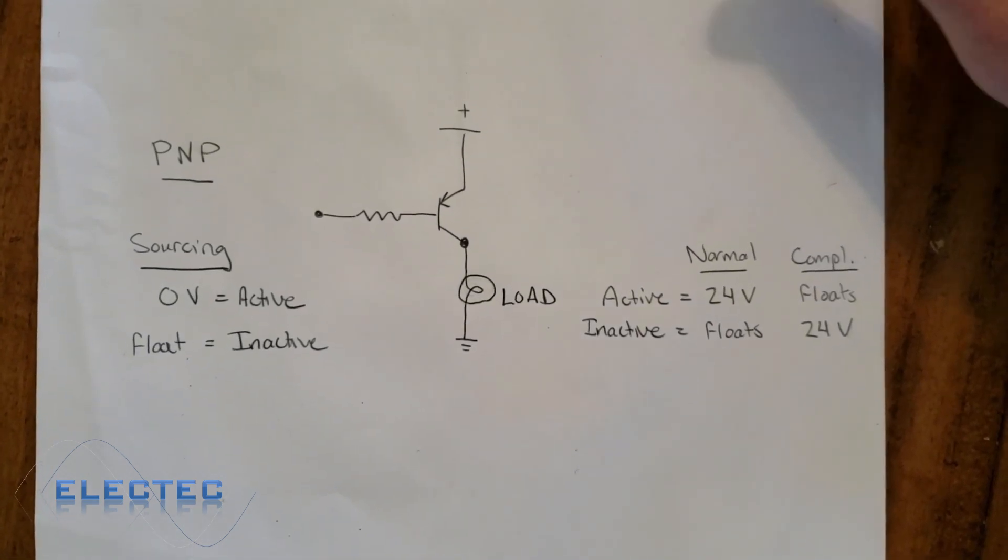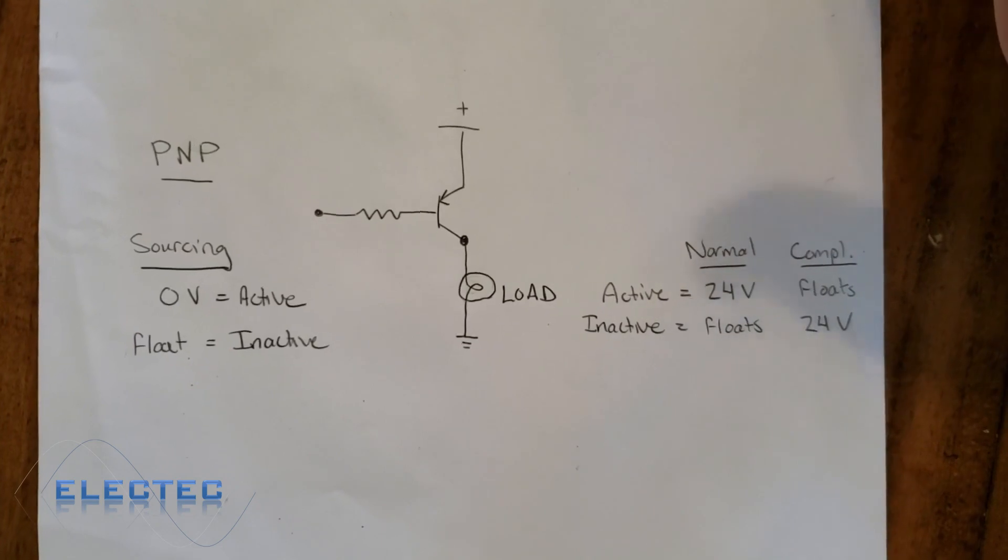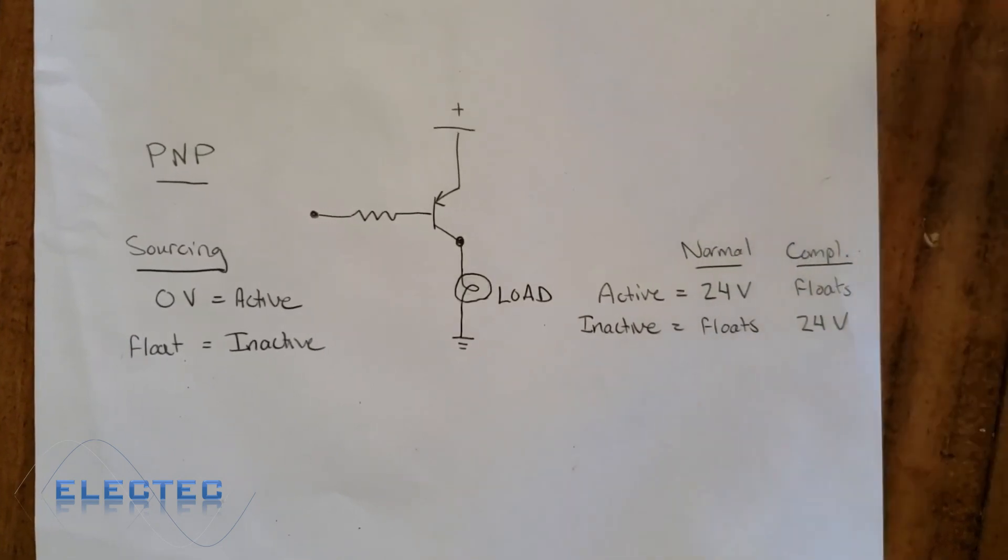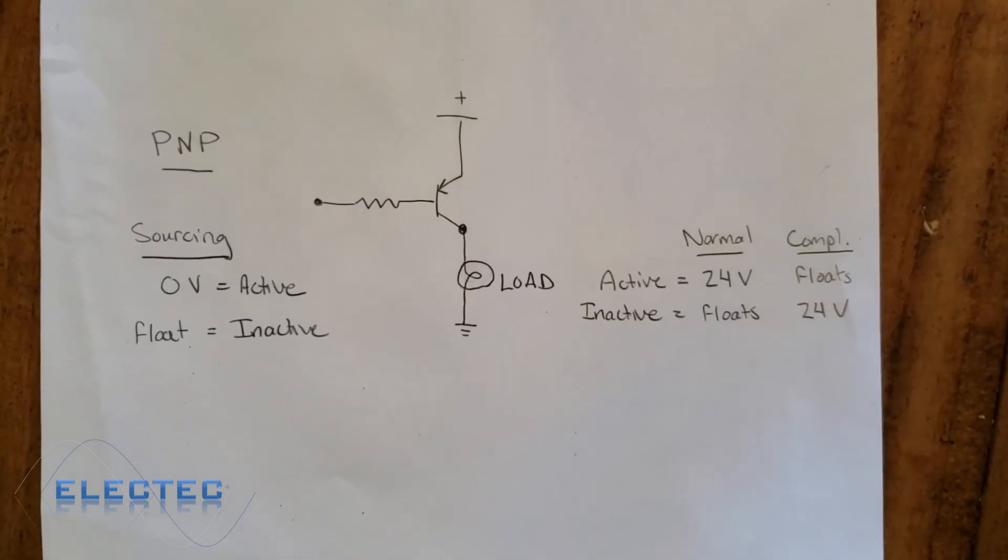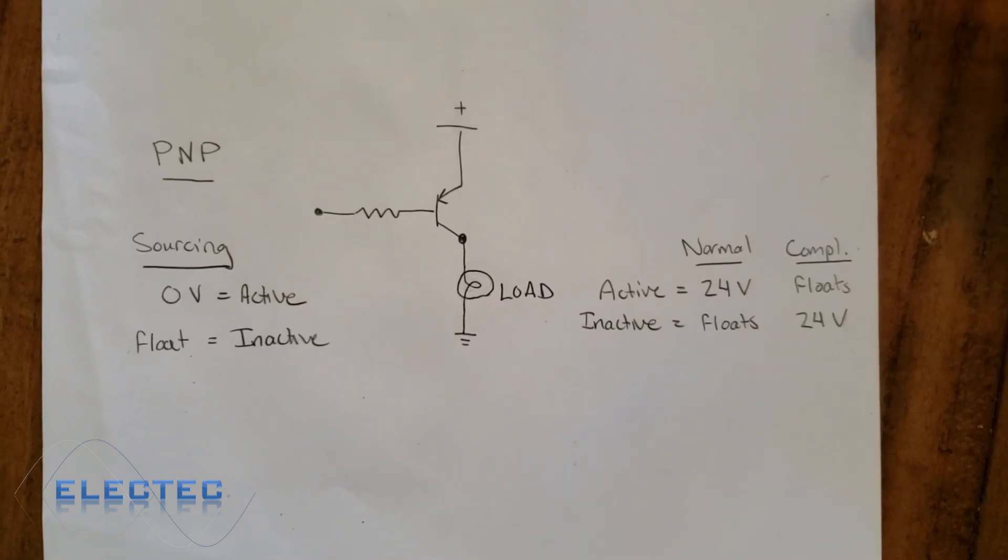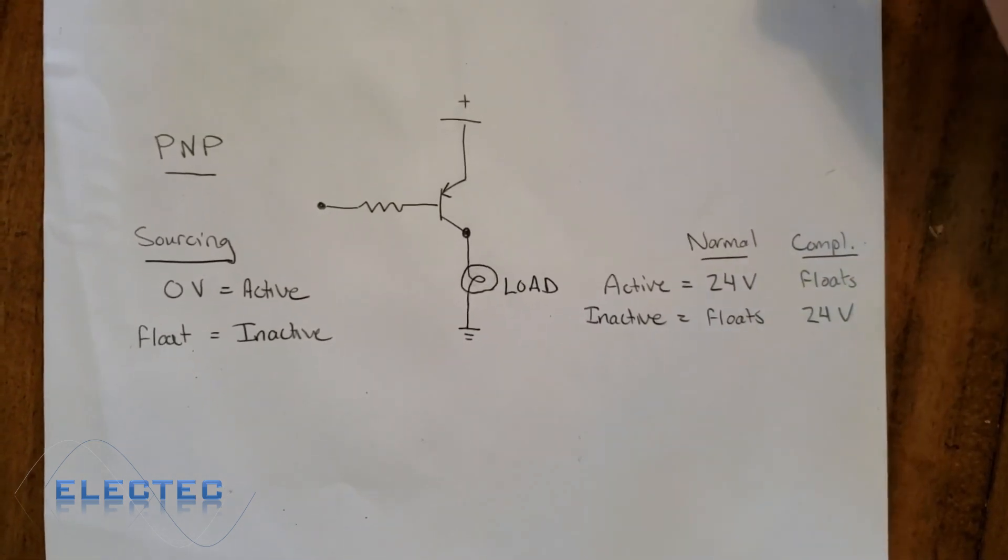If you remember in my first video, sourcing and sinking work together. They have to work together. If you have a sourcing sensor, you must have a sinking input. If you have a sinking sensor, you must have a sourcing input if we're talking about PLCs.